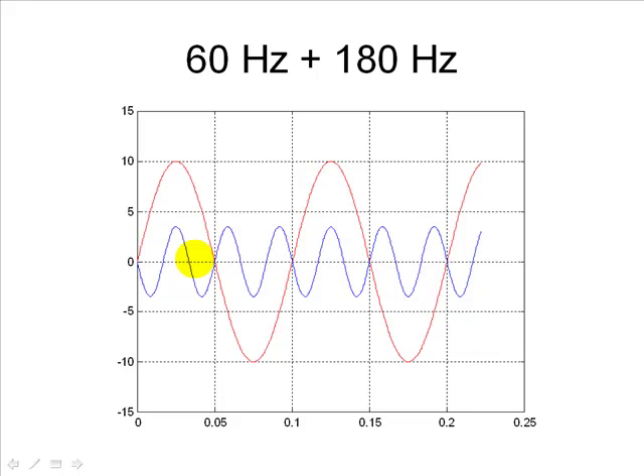In short, to create a sinusoidal flux, we need to have a sinusoidal current of 60 Hz, this one, which we call the fundamental component of the magnetization current. And a triple frequency current, this one, that we call the triple frequency component of the magnetization current. 60 Hz and 180 Hz correspondingly in Canada. In Europe, those would be 50 Hz and 150 Hz.